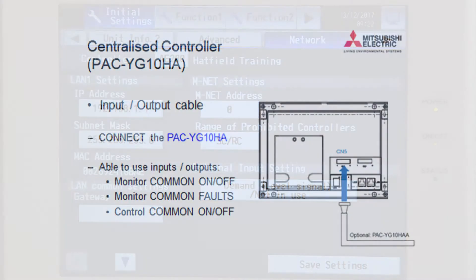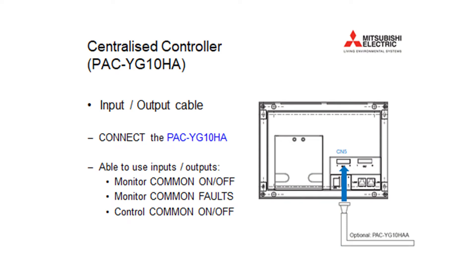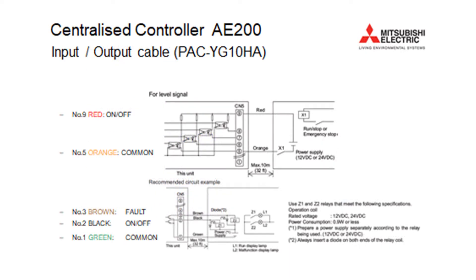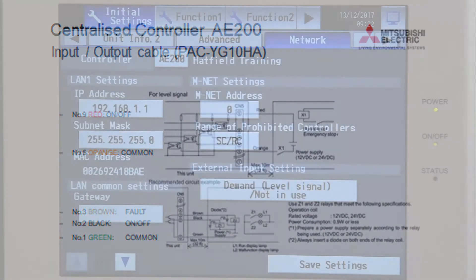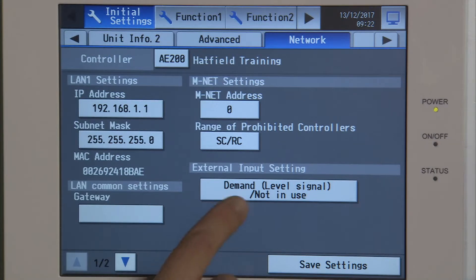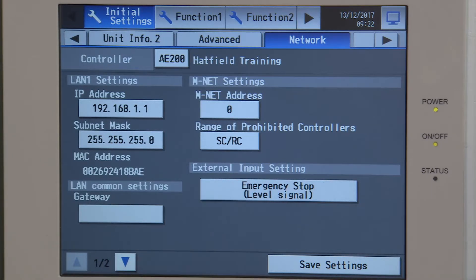On the basis that you have your nine-wire adapter connected to the back of this unit and have it wired onto your contactor — for example, for a fire alarm situation — we can now use that external relay to switch all the air conditioning off in a fire situation. The default setting is set to 'not in use', so though you put the relay in place it won't do anything yet. Click on it once and it now becomes an emergency stop: when you make the contact, the air conditioning will switch off.